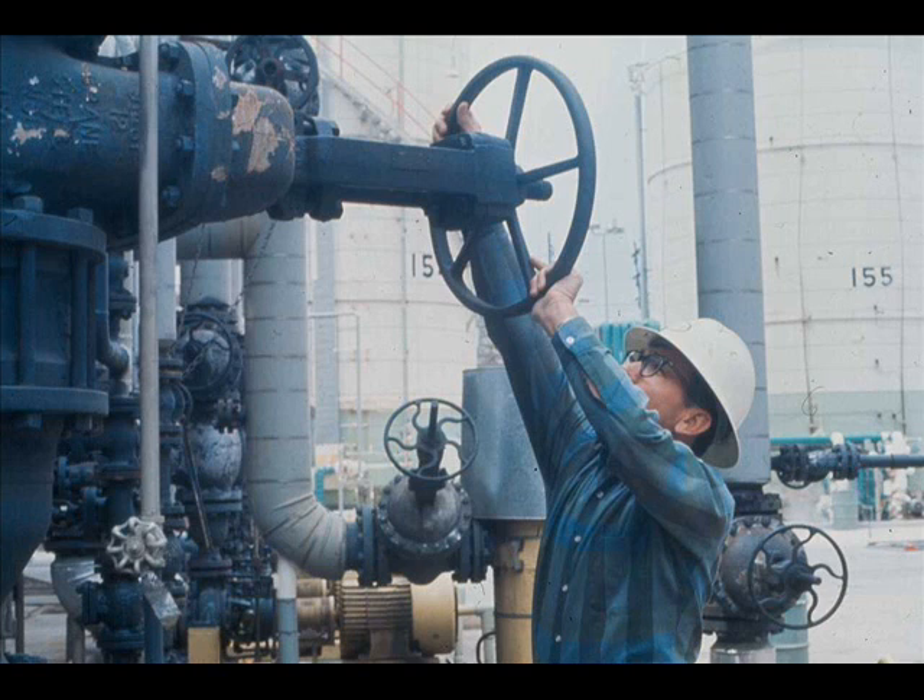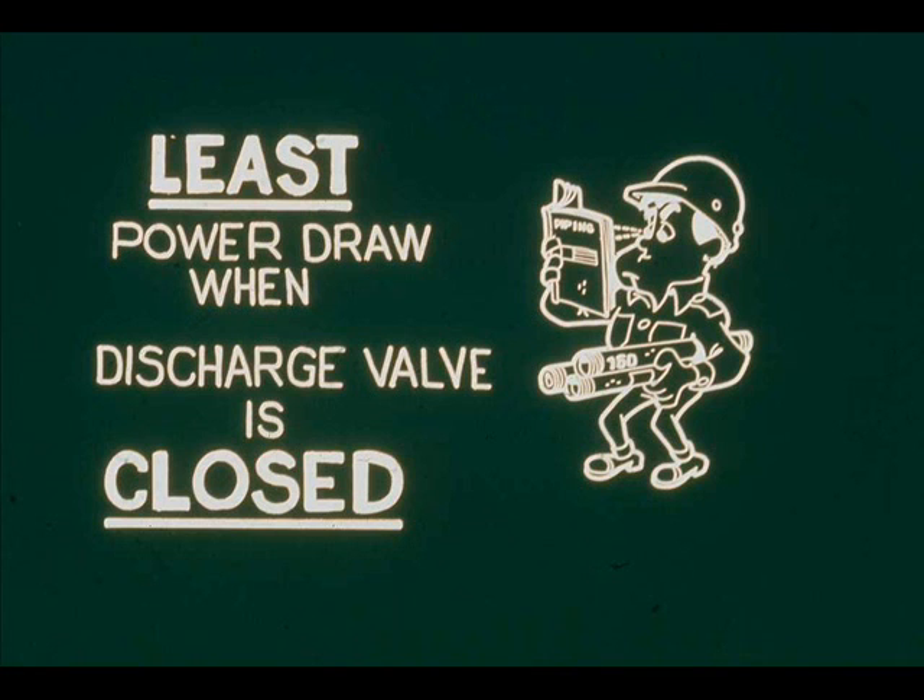Open the discharge valve — how wide depends on the particular pump and driver. In some cases it should be only about 10% open; in others it may be wide open.